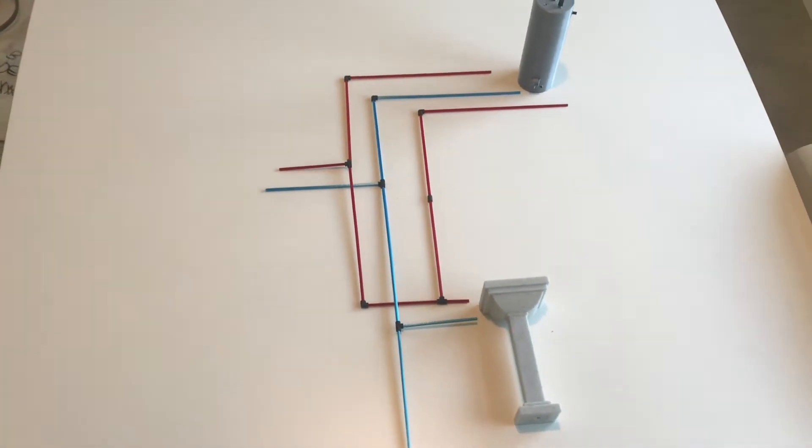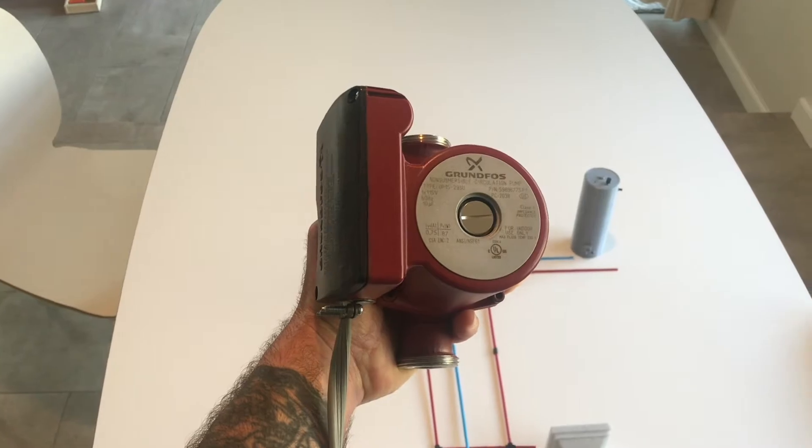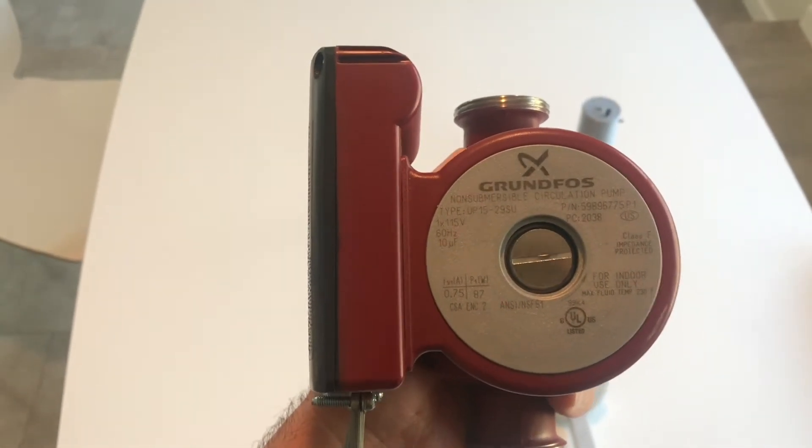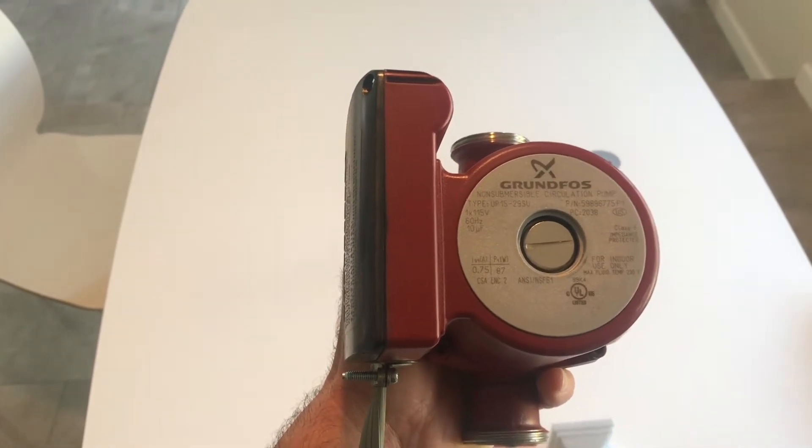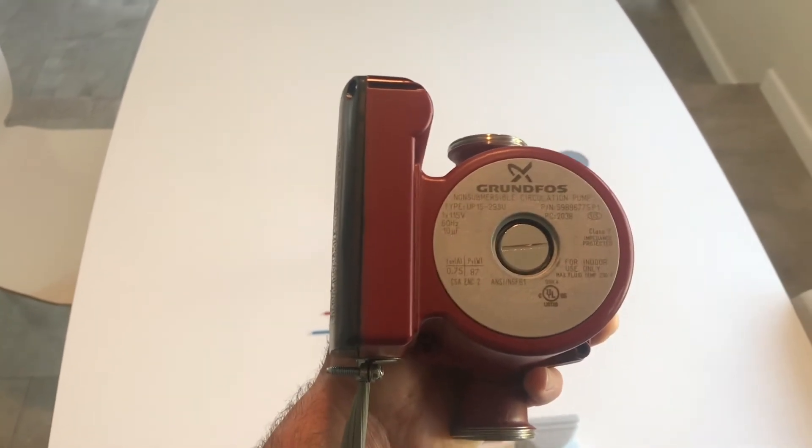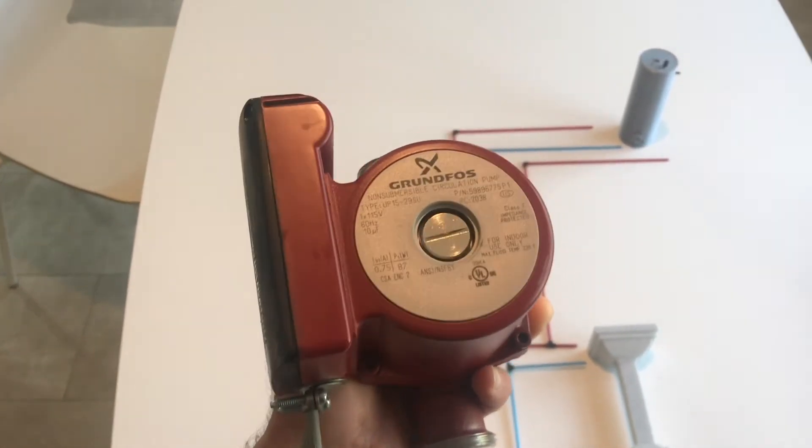That's the cleanest way to do it and my recommendation for a tank water heater. To achieve such a thing you would use a pump that looks similar to this. The brand is Grundfos. The pumps range in price anywhere from a couple hundred dollars to three, four, five hundred dollars depending on the setting. For example if your house is really long and there's a really long stretch of pipe or if there's multiple layers to your house you have to size the pump appropriately.